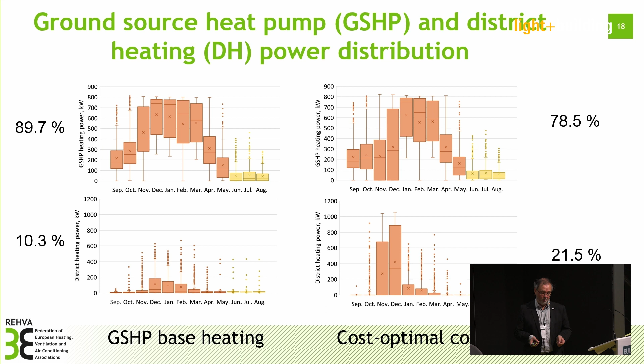We can see the difference here: with normal base heating, about 90% comes from the heat pump and 10% from district heating. But when we take price into account, it makes sense to use more district heating during the hours when electricity is very expensive. In this case, it becomes about 80% ground source heat pump and 20% district heating - so we change quite a lot how we use it.